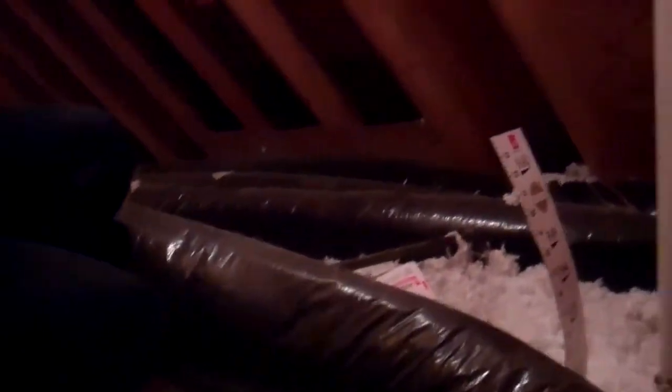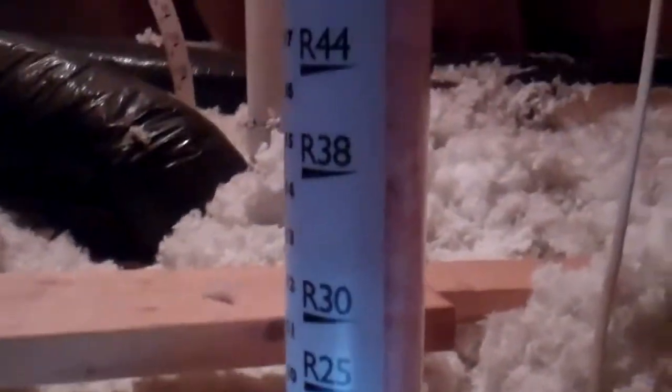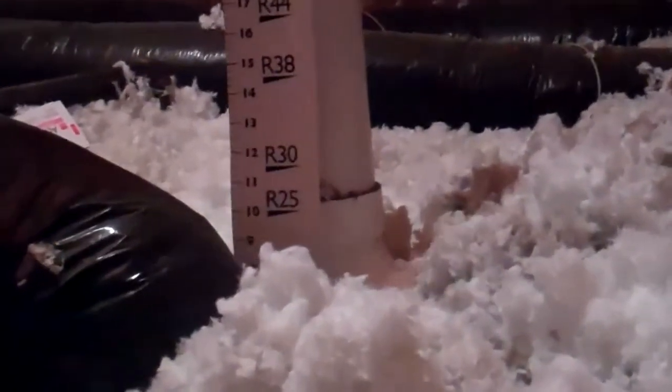to make sure that it's cocooned. Now we're up in the attic, and one of the things that you'll see is blown insulation. Okay, this is blown insulation here. You actually see the ducts that are exposed. One of the things that we try to do is find out the actual insulation level, or the R value, of the insulation up in the attic. And what we're finding is that there are certain spots where it's higher and certain spots where it's lower. As we put a couple tubes of insulation over here, we see that in this particular instance, it's well below the R19 level. In some instances here, we have about an R25 level. On average, just looking around the attic, because a lot of it is compressed, I'm going to say we have approximately an R20.